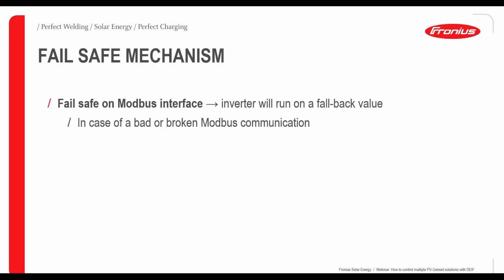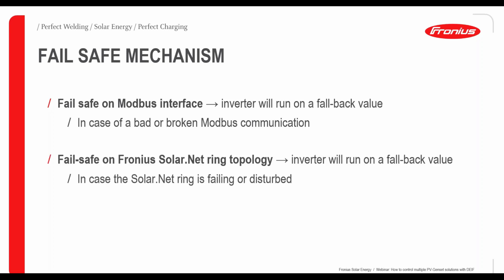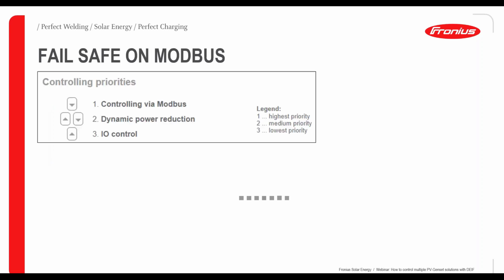So one last thing I want to mention is the failsafe mechanism. That's related to the slide we just saw. Why did we do the clustering of the SolarNet and Modbus? If the Modbus is failing, the communication line is broken, something happened, the inverter will run on a fallback value, which I can set. I will show you in the next slide. The same applies to the SolarNet ring. If anything happens in this SolarNet cluster, in this SolarNet ring, the inverter will run on a fallback value, which I can set. So now the question, where can I set this?